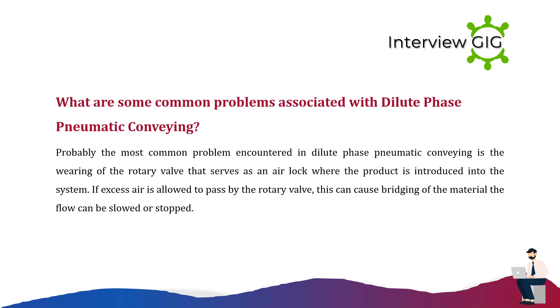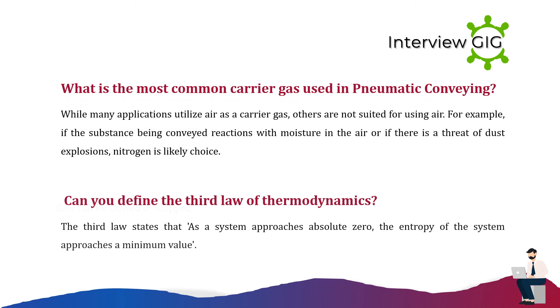What are some common problems associated with dilute phase pneumatic conveying? The most common problem is the wearing of the rotary valve that serves as an air lock where the product is introduced into the system. If excess air is allowed to pass by the rotary valve, this can cause bridging of the material, and the flow can be slowed or stopped.